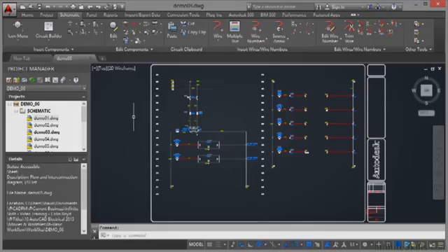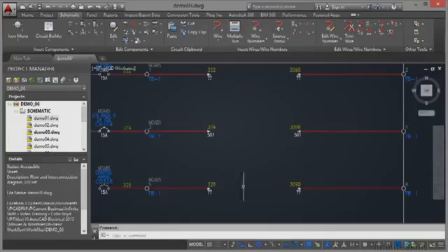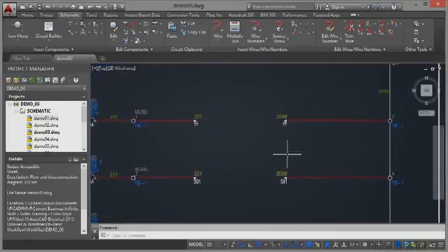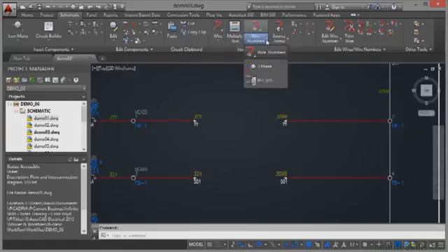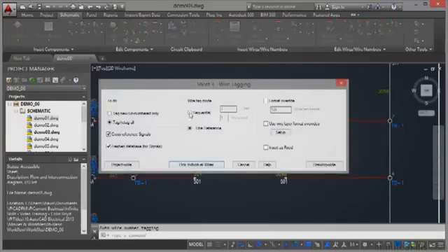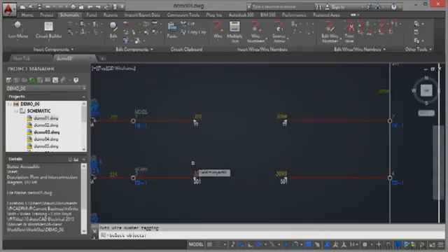So, for example, you might want to number a wire, let's say. We've got some wires over here in drawing 03, so let's zoom in. And what I'll do is I'll just pan down this way a little bit, and there's a wire there. So if I come here, wire, like so, there's the wires there, but I need to wire number it. So I go over here to wire numbers. There we go, wire numbers there. I can tag if I want to, like that. Pick an individual wire. So I'll select that wire there, press enter to confirm, works out the wire numbering for me and adds that to the list.